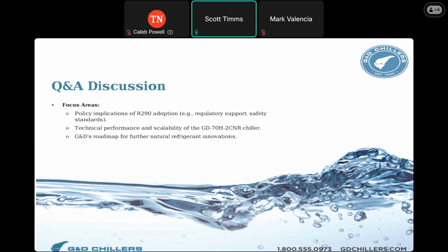The main driver is cold storage rooms. That type of refrigeration is not a niche product like a glycol chiller, it's a widely available commodity product. So you can buy direct refrigerant cold room equipment for very, very cheap. And since it's direct refrigerant, it's more efficient. The glycol is kind of a middleman we need since we're pumping it through a bunch of different tanks. You can't send refrigerant directly to those efficiently, or in a way that promotes the equipment lasting very long, so you end up having to use glycol instead. Whereas in the cold room, you can just use direct refrigerant, which is very, very efficient. So in general, I would say don't combine them.